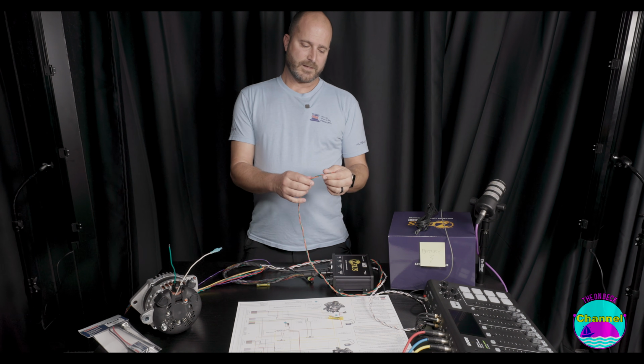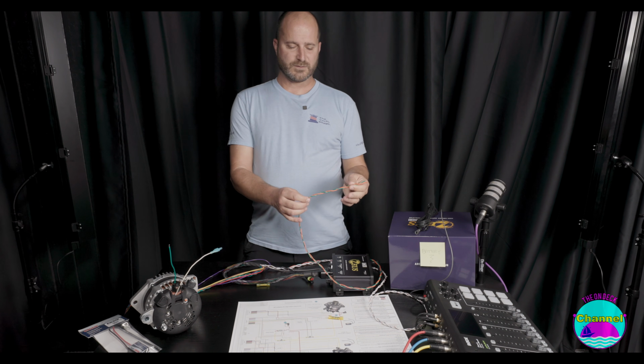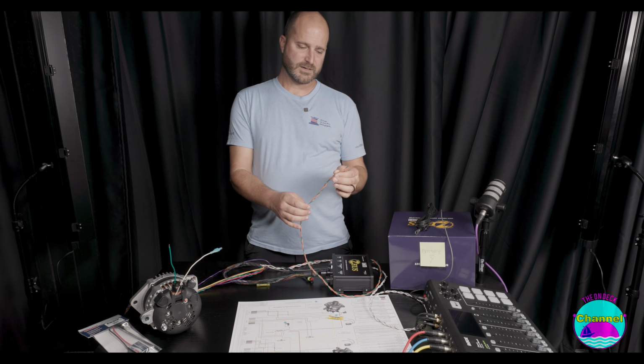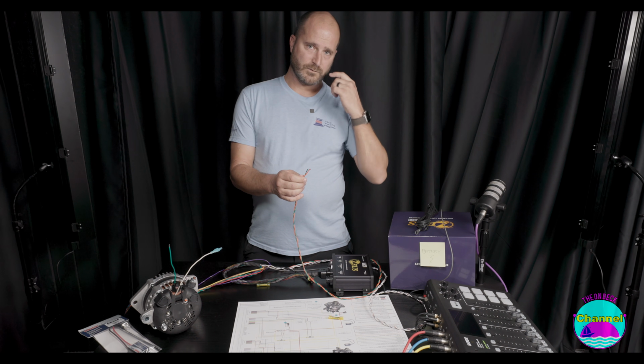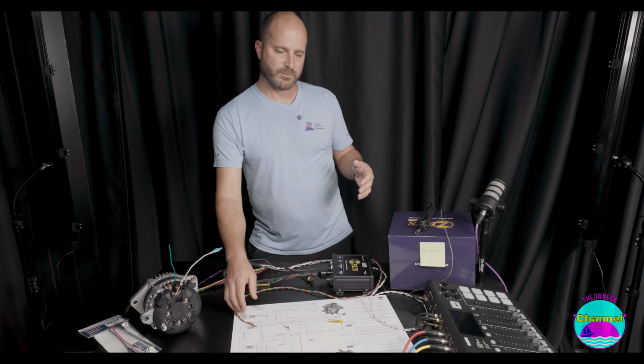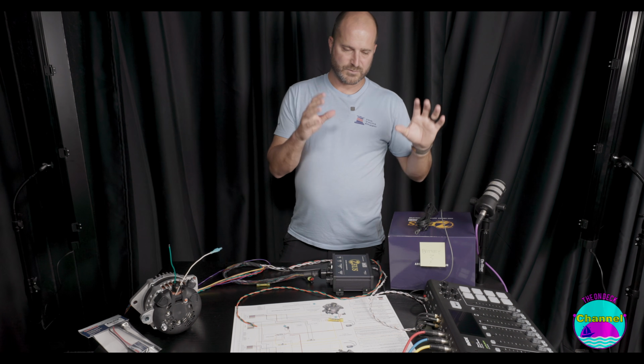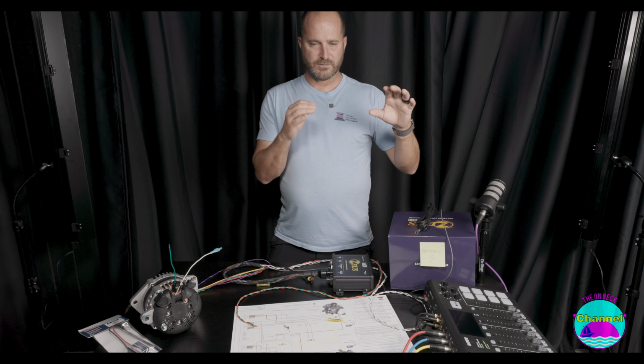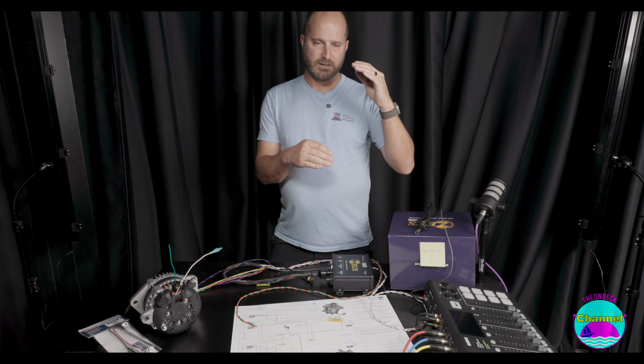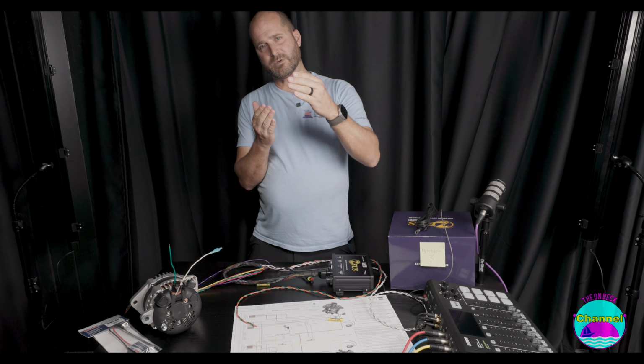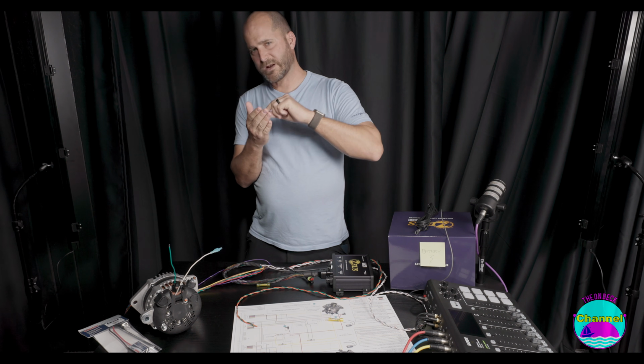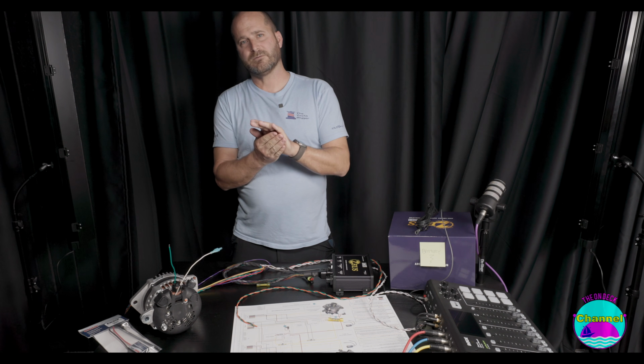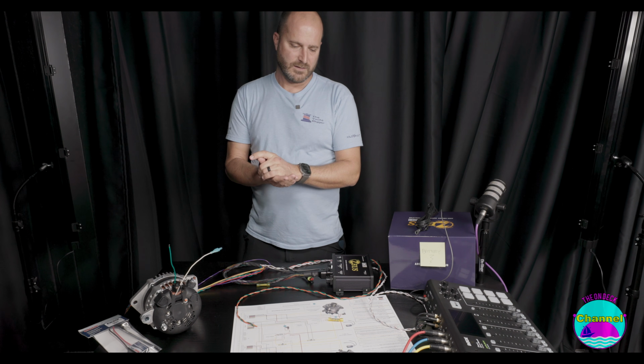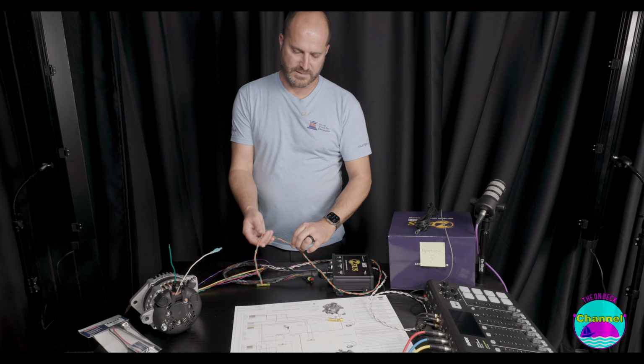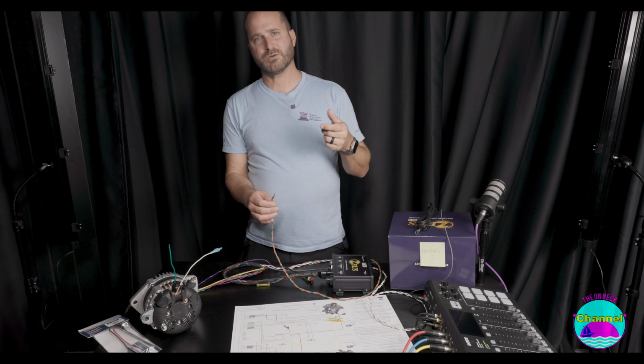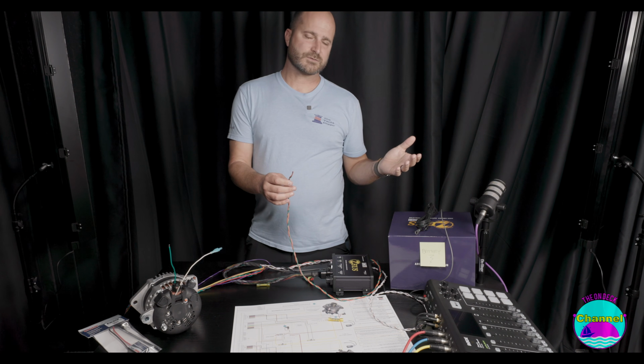Although not required, I still prefer a twisted pair for these wires, and it's important to put an inline fuse where you measure. Typically on a battery bank, I'll have the bank, a distributor, and a shunt—depending on whether it's a Victron or not—and a Class D fuse with an MRBF fuse holder. Right after the protected side of the Class D fuse is where you grab your measurement for the voltage sense. Same with the negative: after the distributor, find a spot as close to the battery as possible.